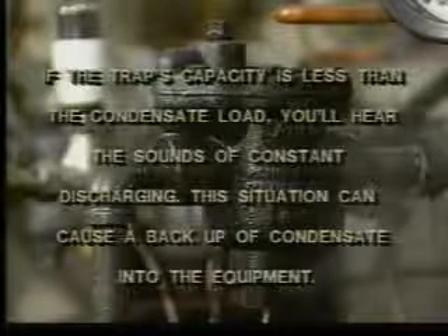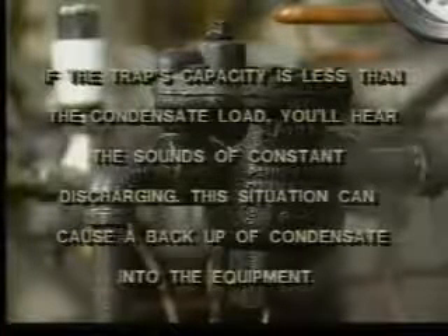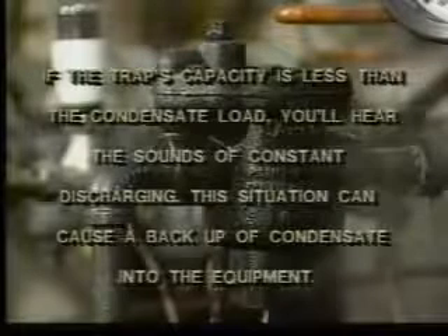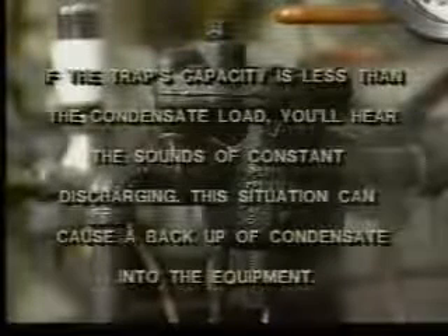The sound of continuous condensate discharge is heard when the trap is undersized. If the trap's capacity is less than the condensate load, you'll hear the sounds of constant discharging. This situation can cause a backup of condensate into the equipment.